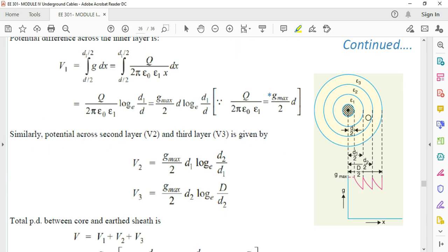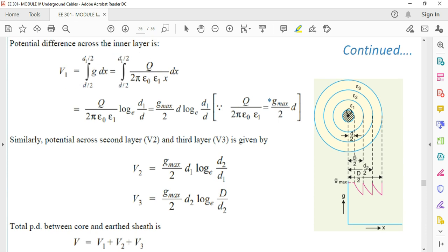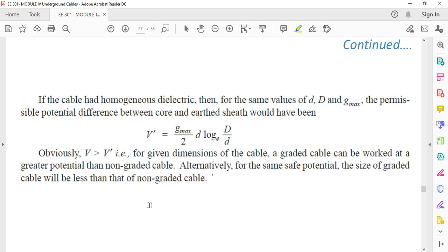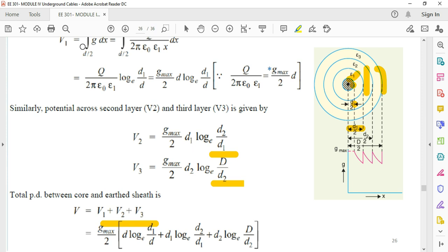This is the dielectric structure. The potential difference across the inner layer is V1 = ∫(d/2 to d1/2) g dx = (Q / 2π·ε₀·ε1) · ln(d1/d), giving V1 = (Gmax/2)·d·log(d1/d). Similarly, V2 = (Gmax/2)·d1·log(d2/d1), and V3 = (Gmax/2)·d2·log(D/d2). The total potential difference between core and earth sheath is V = V1 + V2 + V3.